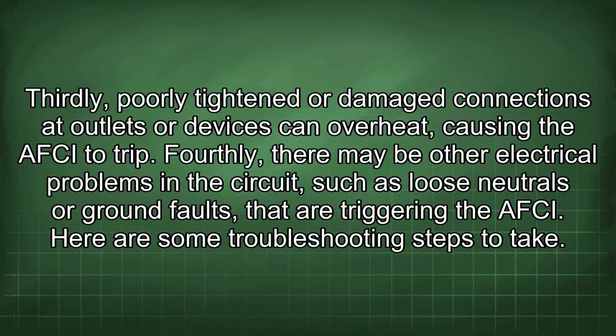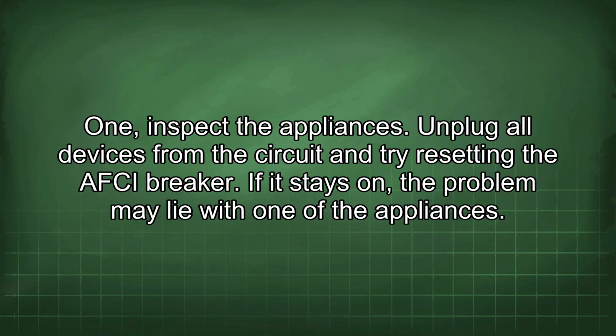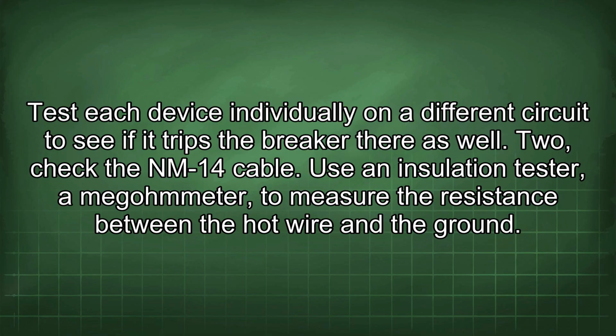Thirdly, poorly tightened or damaged connections at outlets or devices can overheat, causing the AFCI to trip. Fourthly, there may be other electrical problems in the circuit, such as loose neutrals or ground faults, that are triggering the AFCI. Here are some troubleshooting steps to take. 1. Inspect the appliances. Unplug all devices from the circuit and try resetting the AFCI breaker. If it stays on, the problem may lie with one of the appliances. Test each device individually on a different circuit to see if it trips the breaker there as well.